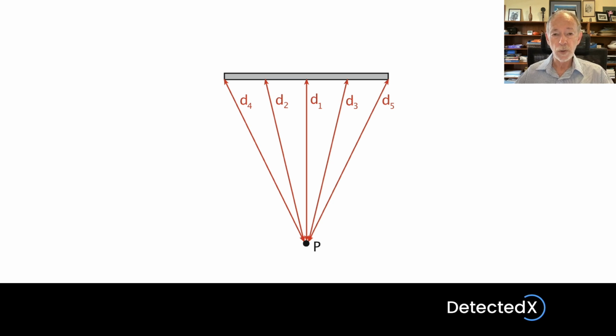Now we come to some simple geometry. The distance D1 is the shortest of these paths. So the ultrasound transmitted from the centre of the transducer will arrive first at the point P. D2 and D3 are a bit longer, and therefore the ultrasound energy transmitted from those points on the transducer will arrive a bit later at the point P.